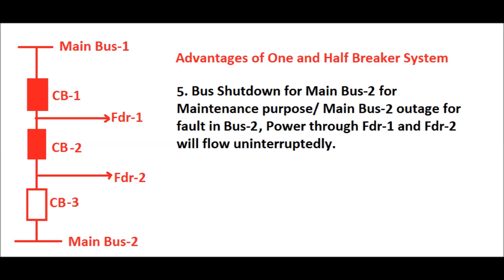From an operational point of view, the one and half breaker system offers greater flexibility — the switching operations of feeder 1 and feeder 2 are more flexible via main bus 1 and main bus 2. However, since three circuit breakers are used for two feeders, this system is more costly. Additionally, there is complexity in the protection system associated with the one and half breaker configuration.